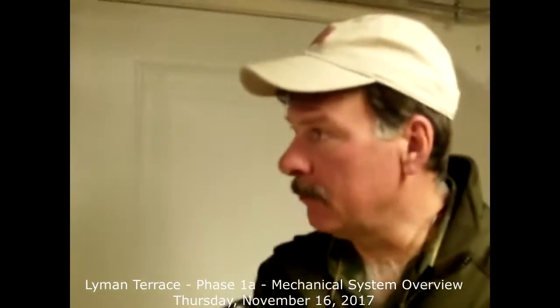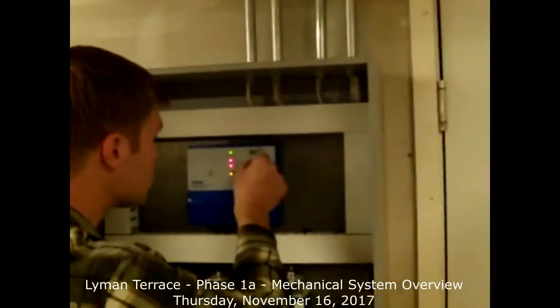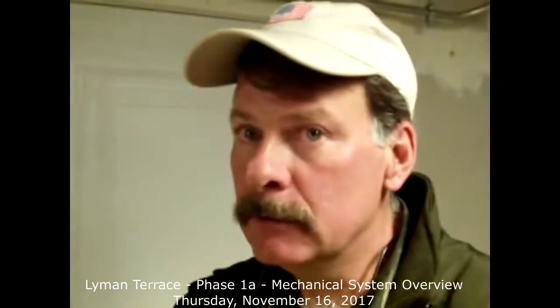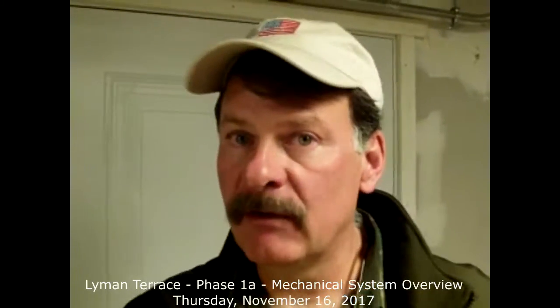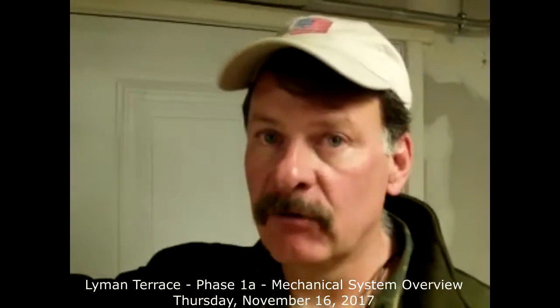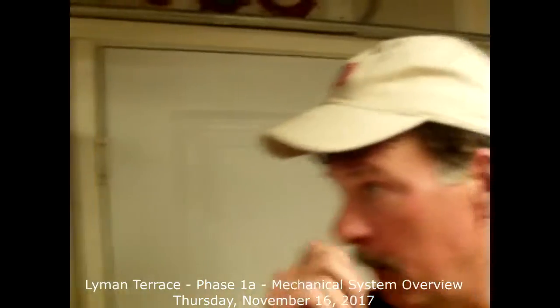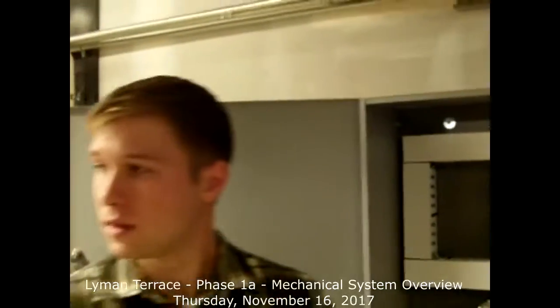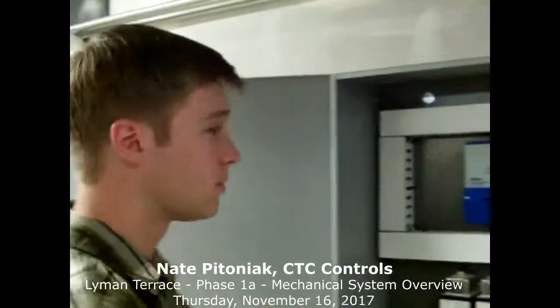And on that note, I'm going to suggest that we jack that up to like 72. Yeah, because there's a high variance in temperature sensors, and I don't want the boiler firing when the pumps aren't running. Right, because that'll give you one of your lockouts. So the boilers have their own outdoor sensor. It doesn't know what this box is reading on its outdoor sensor. This is an accessory that the engineer wanted. It's not a boiler accessory, it's an accessory for the pumps. Okay.